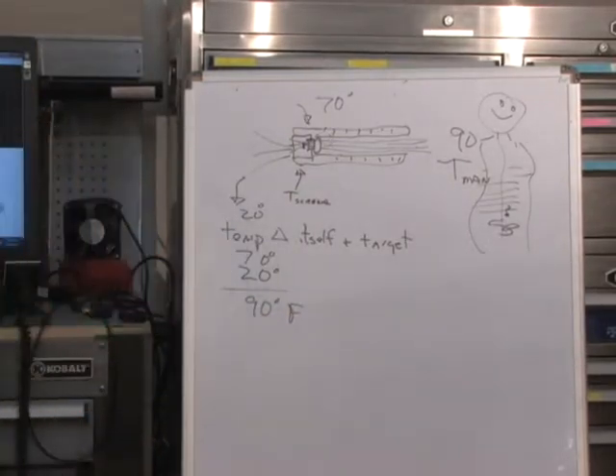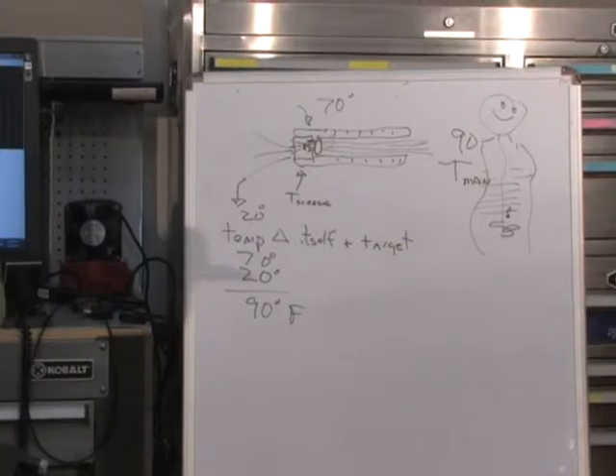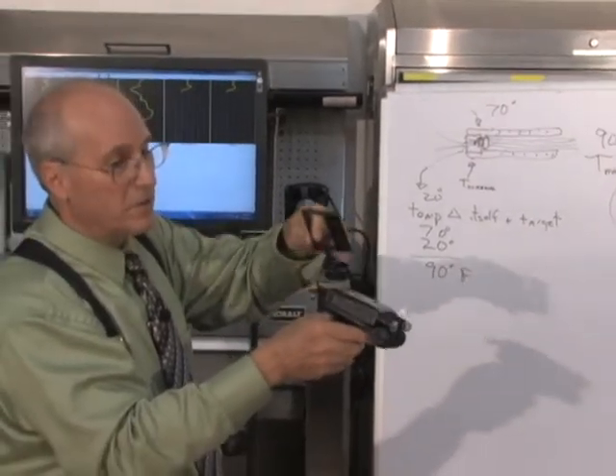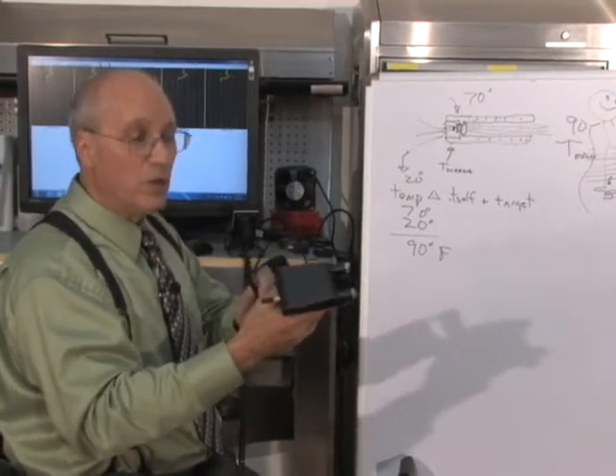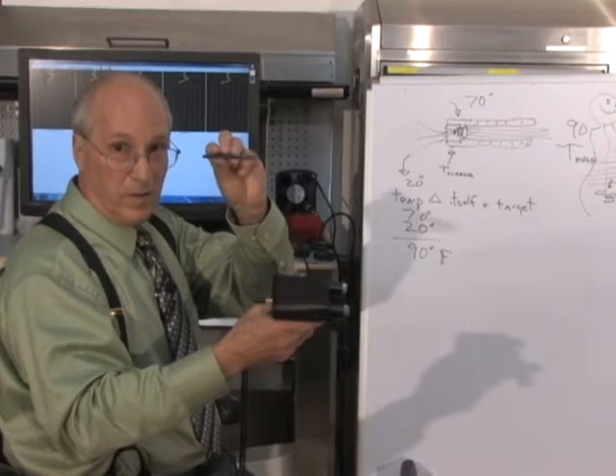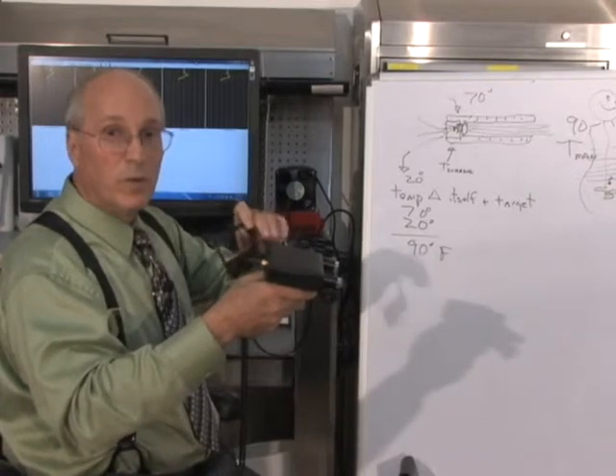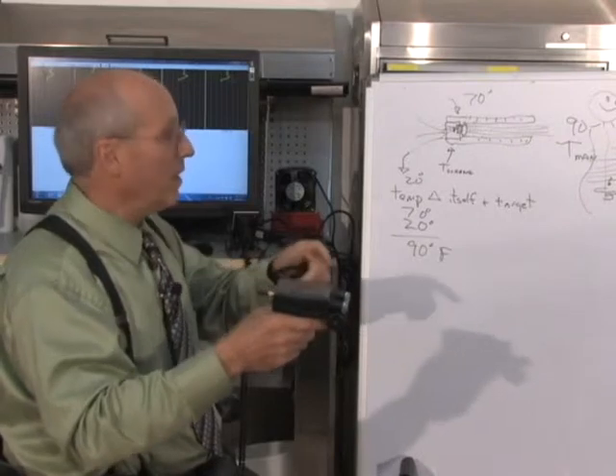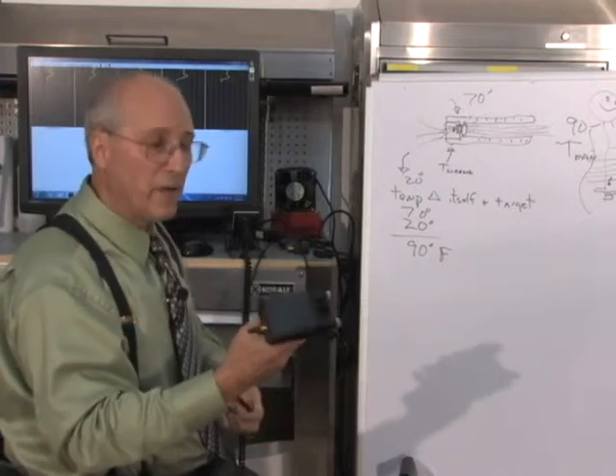This is why when you are using the scanner, we have a thermal barrier or a gasket between the head of the scanner, which houses the infrared sensors and the handle. As you can appreciate as you hold the scanner, you will warm up the handle. The gasket or thermal barrier allows the head to only warm up very, very slowly. Any slow changes in temperature of the head are compensated for within the circuitry and we remain reading very accurately.